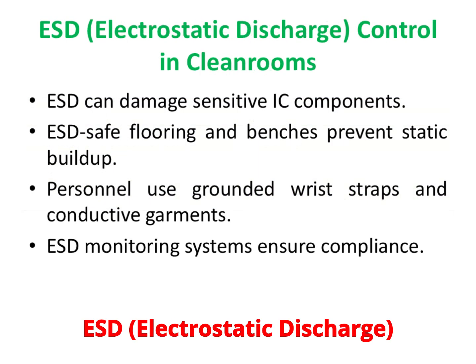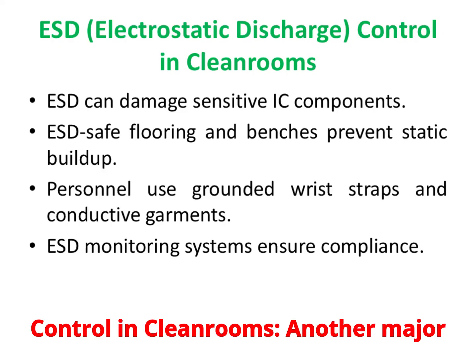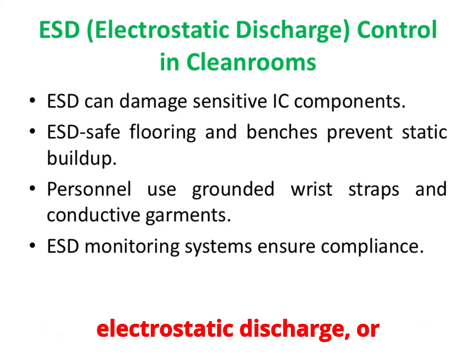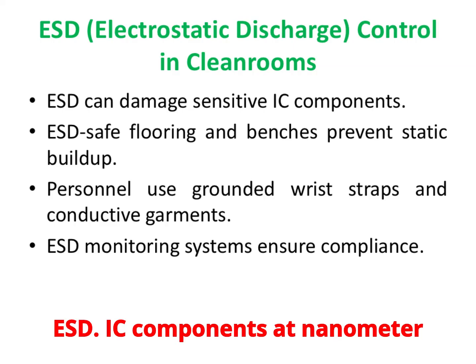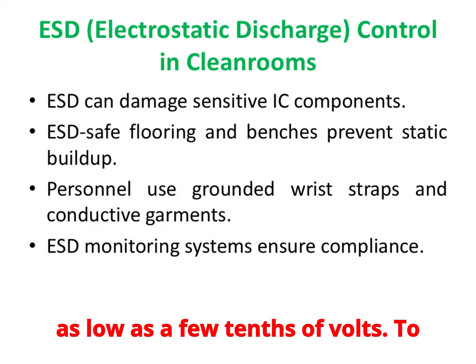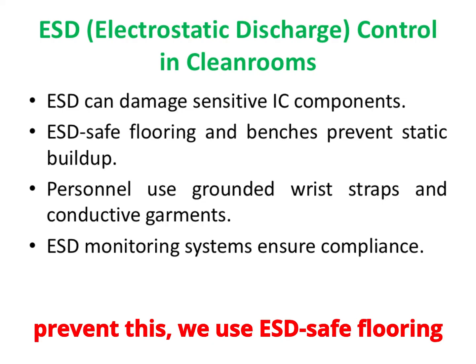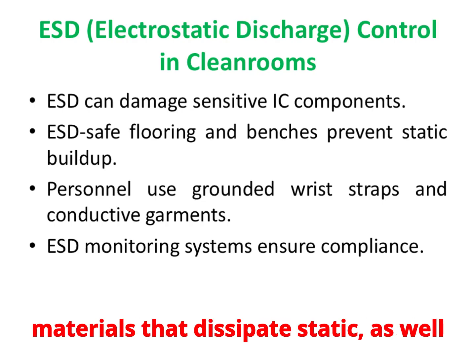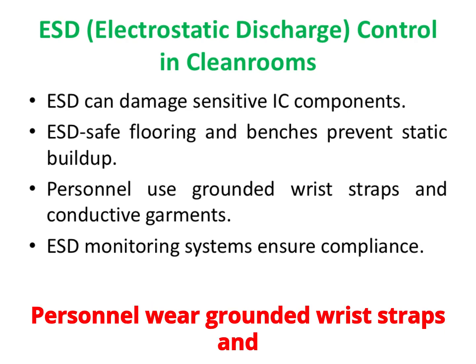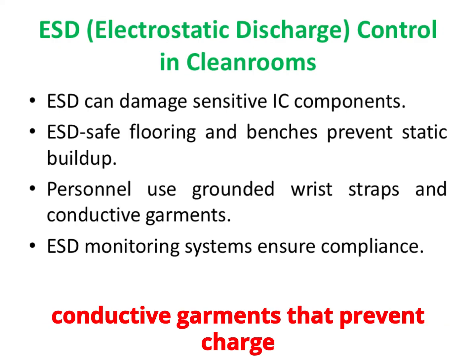Another major risk in clean room environments is electrostatic discharge, or ESD. IC components at nanometer technology nodes are extremely susceptible to damage from static charges as low as a few tens of volts. To prevent this, we use ESD-safe flooring materials that dissipate static, work benches with conductive surfaces, personal grounded wrist straps, and conductive garments that prevent charge buildup.